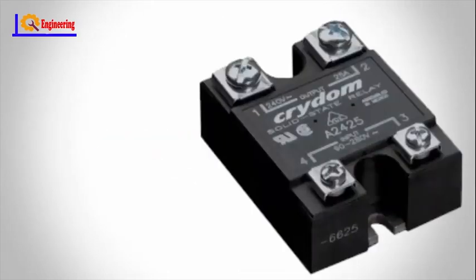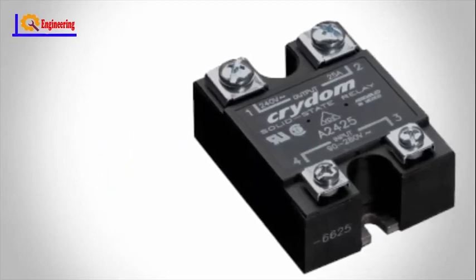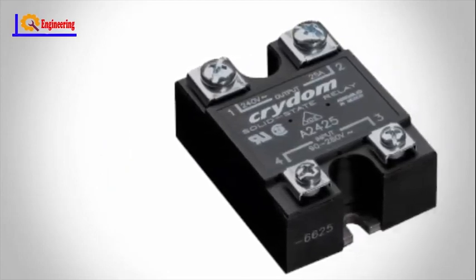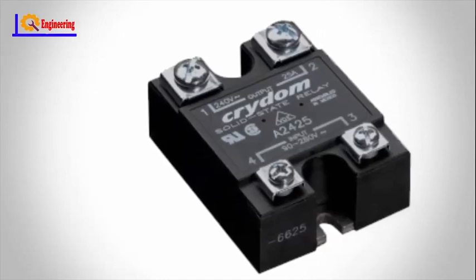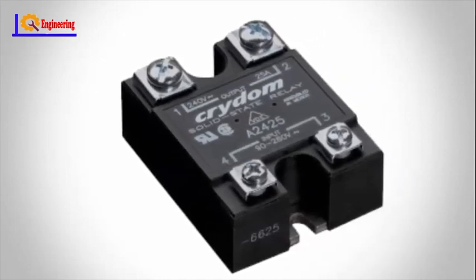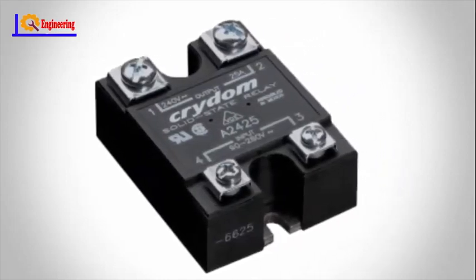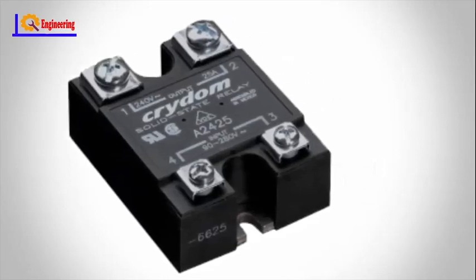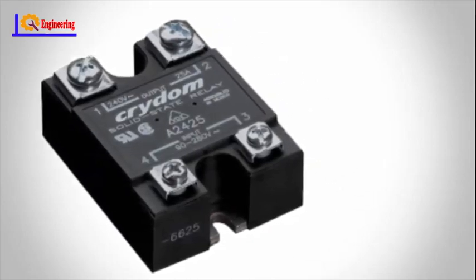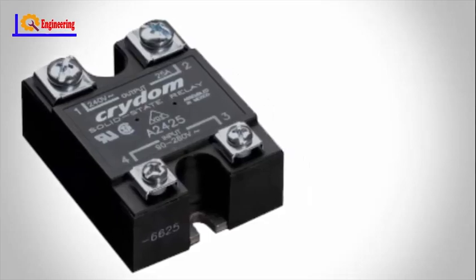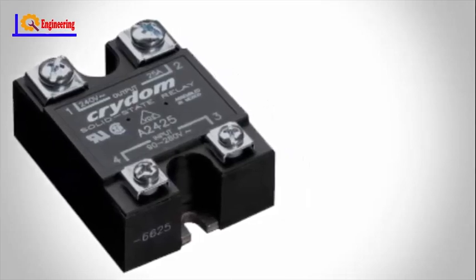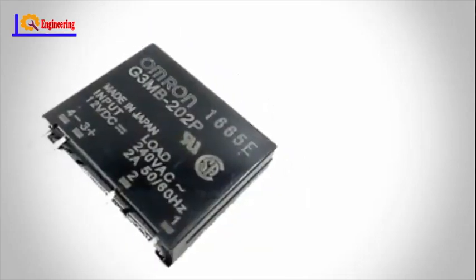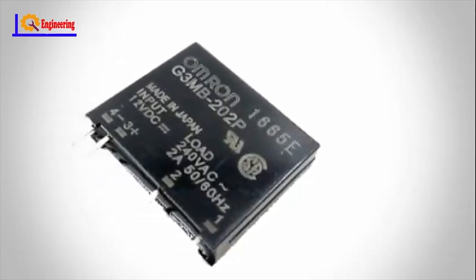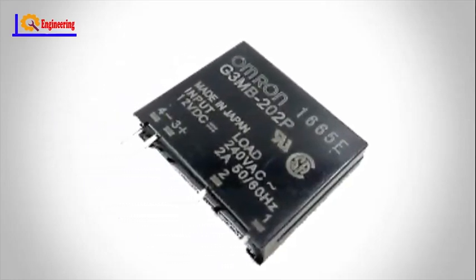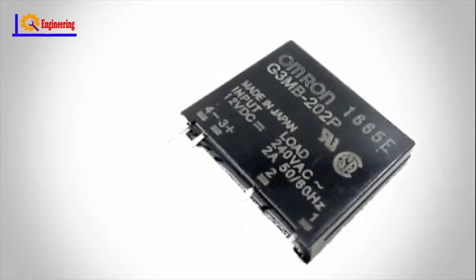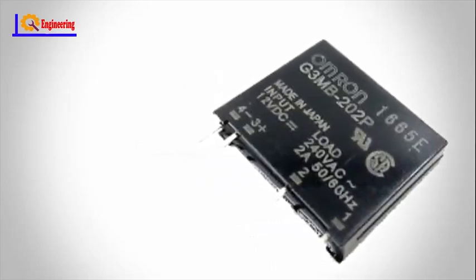Solid-state relays. Solid-state relays use solid-state components to perform the switching operation without moving any part. Since the control energy required is much lower compared with the output power to be controlled by this relay, that results in a higher power gain when compared to the electromagnetic relays. These are of different types: reed relay, coupled SSR, transformer coupled SSR, photo-coupled SSR, and so on.